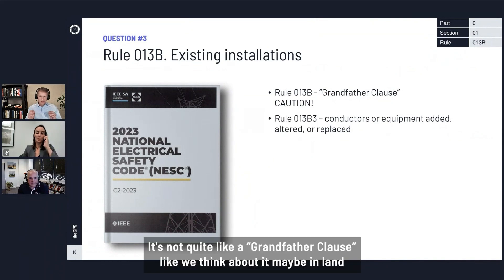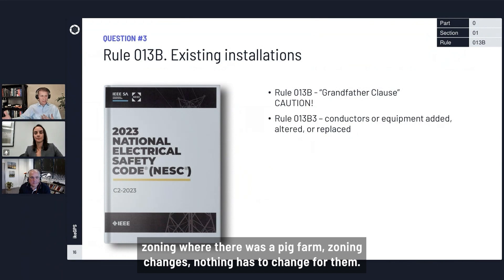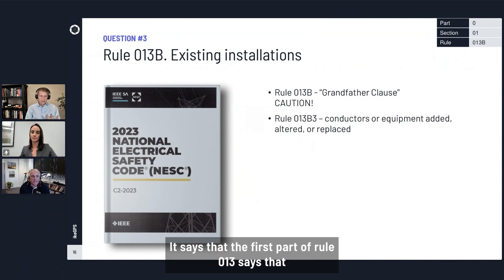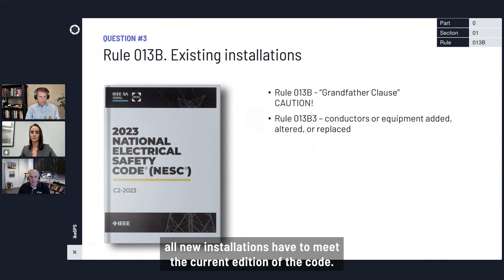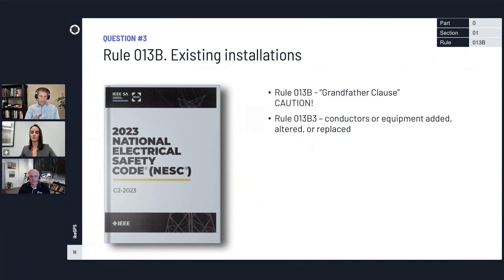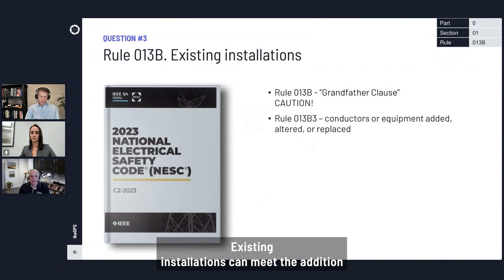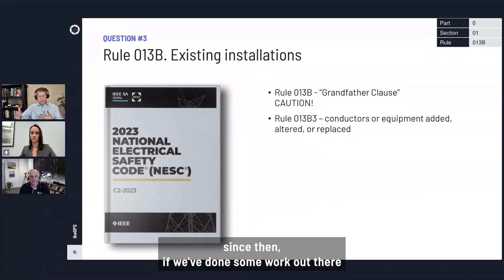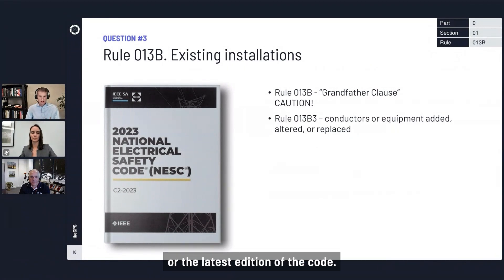It's not quite like a grandfather clause as we think about it in land zoning — where, say, a pig farm exists and zoning changes but nothing has to change for them — but it is a little bit like that. Rule 013 says that all new installations have to meet the current edition of the code. Existing installations can meet the edition in effect when they were installed, any edition they've been brought up to since, or the latest edition of the code.